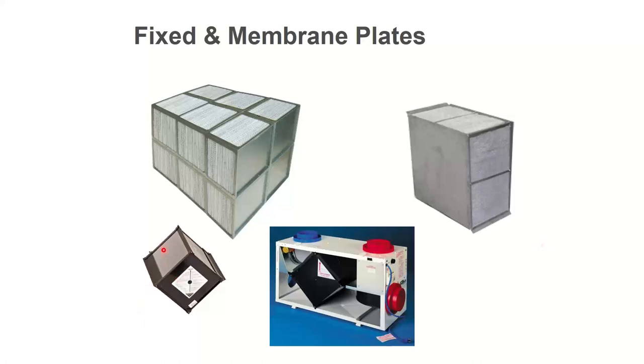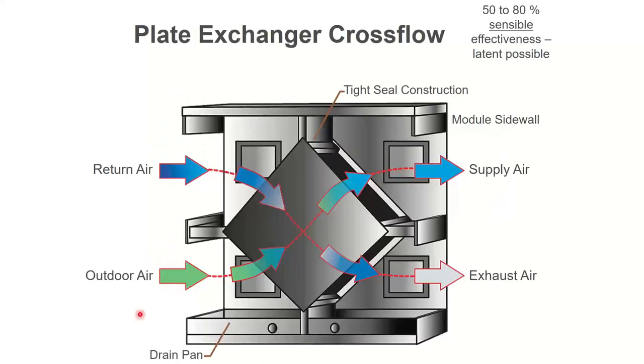Fixed plates, I can get metal plates that do only sensible, or I can get ones that have a fibrous material in them where I can do sensible and latent transfer. So the way that would look, I have two air streams. I crisscross them. This return air goes through the heat exchanger this way. The outside air coming in goes through the heat exchanger that way. Those two air streams don't touch each other. They go through sleeves, if you will, through pockets on the heat exchanger. Just like if you had an evaporator coil, that's a heat exchanger. I got refrigerant on one side, air on the other, right? They don't ever touch each other.